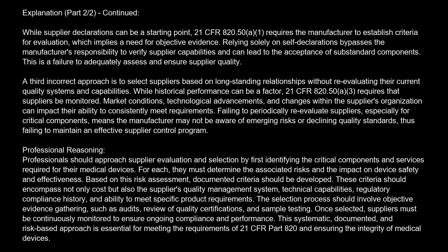Requires the manufacturer to establish criteria for evaluation, which implies a need for objective evidence. Relying solely on self-declarations bypasses the manufacturer's responsibility to verify supplier capabilities and can lead to the acceptance of substandard components. This is a failure to adequately assess and ensure supplier quality.